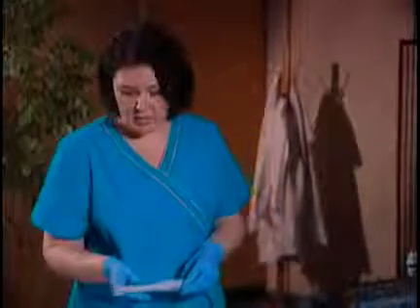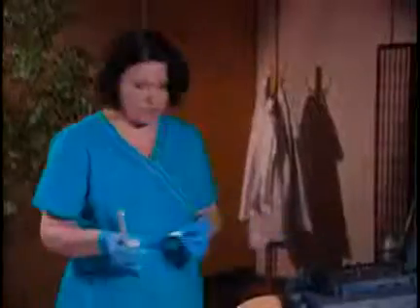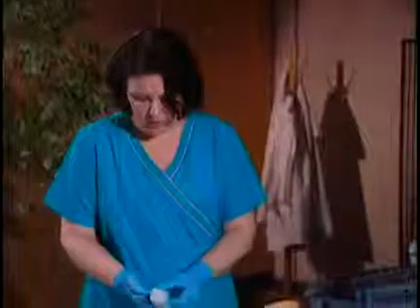So the first stage of the prep for the intracavitary transducer is that we need to cover it with a sheath. When you do this, we need to remove any air gaps that are inside the sheath next to the transducer face. So what we will do is we'll put a little bit of gel inside the cover, position that over the tip of the transducer, and then just pull down the covering over the transducer and pull this down right over the handle so you've got good coverage.